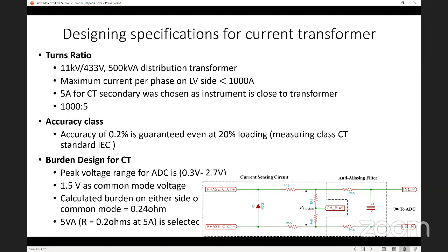Now what is the application of this? My application is mostly for measuring, not for protection purposes, so I'm looking for a 0.2% accuracy CT which you can select. But if you want to use it for protection purposes, you can go for protection class CTs in your system.